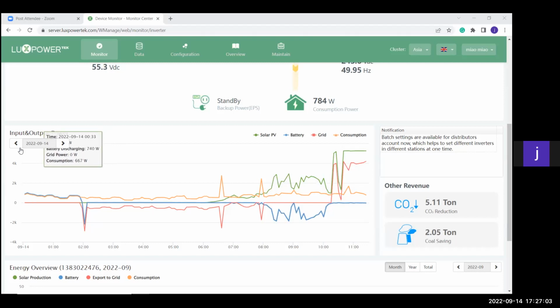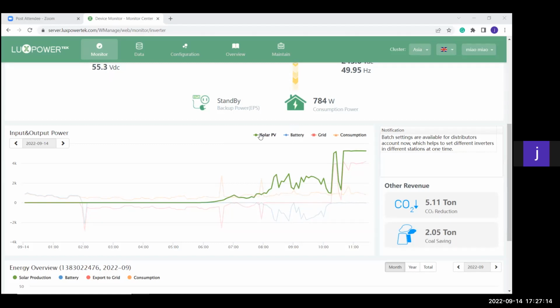You have your date here that gives you what day it was, and then the color configuration at the top: the solar, battery, grid. If you keep it on the solar, it highlights the solar graph, so you can see what your solar did at which time, what the power was. On the batteries, you can see the discharge and the charge at that moment. In this instance, the batteries were charged a little bit and then stopped. Then the grid, that was what the grid was doing at that certain time. And then the consumption, you can see the loads, what the client has done.